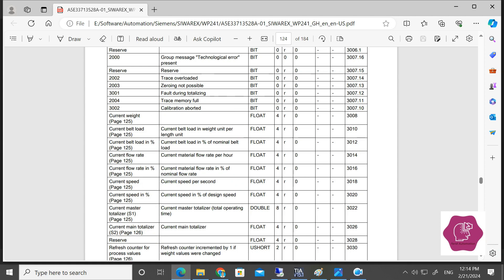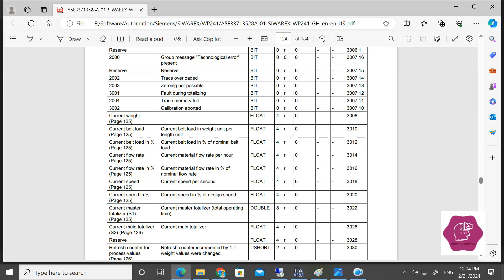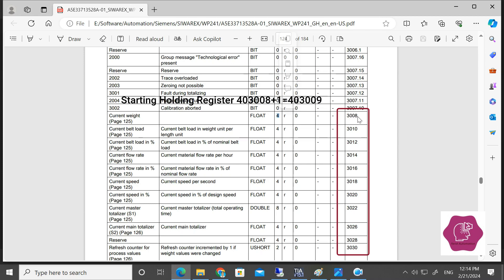If we take the current weight, our starting address will be 3008. This is the holding register and it will be a read register — read data. The data type is float and it is 4 bytes. So for the holding register, it is an extended holding register: 40 then 3008.